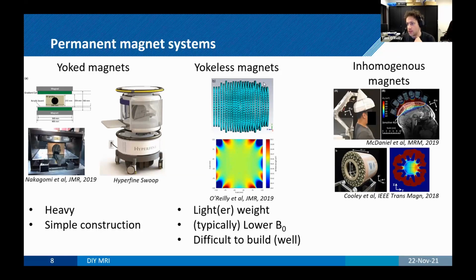The yokeless magnets typically come in the form of Halbach arrays. You don't see these built as often as the yoke designs, just because they're a little bit harder to build and they have slightly lower magnetic field strength, but they're much lighter in weight. So this is the one from our group, which weighs about 75 kilos. It's a hole for imaging the entire human head. So it's very comparable in field distribution to this, but we're at 75 kilos versus several hundred kilos. But these are hard to build, and I'll come back to that later.